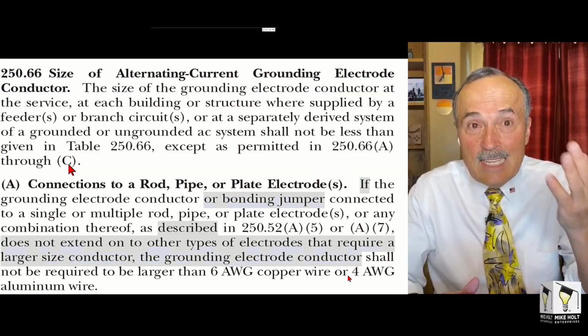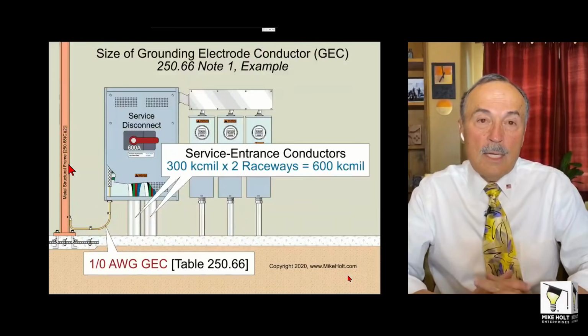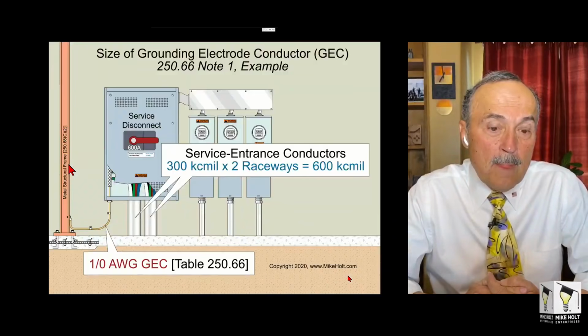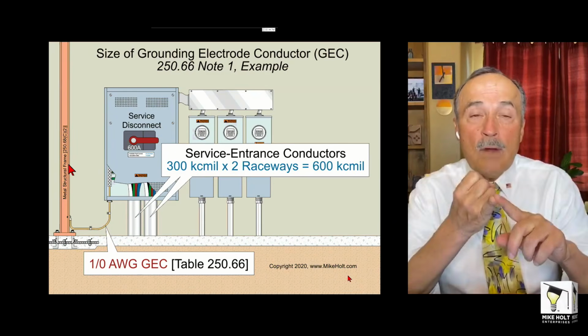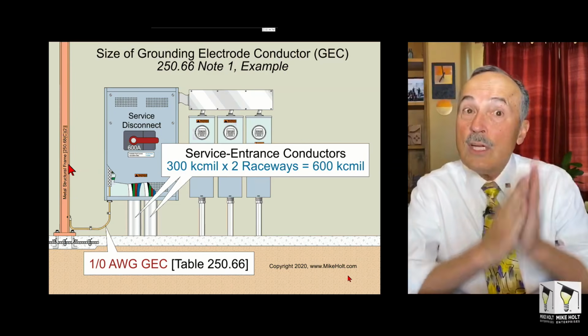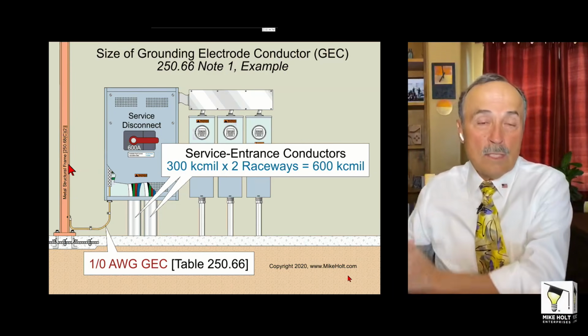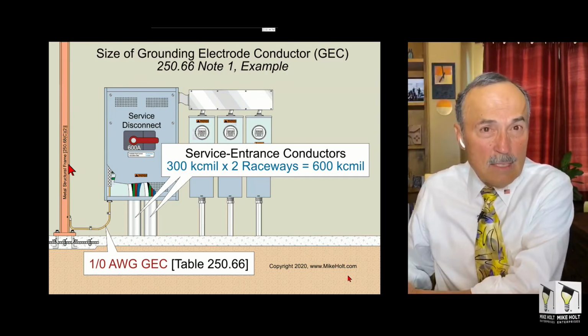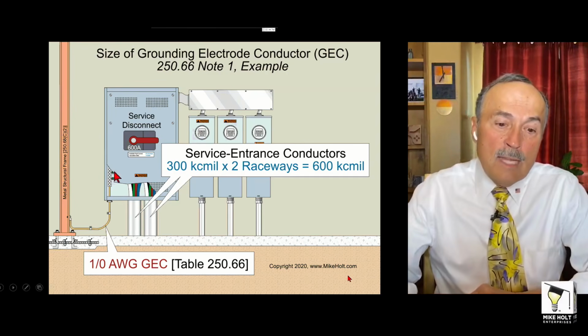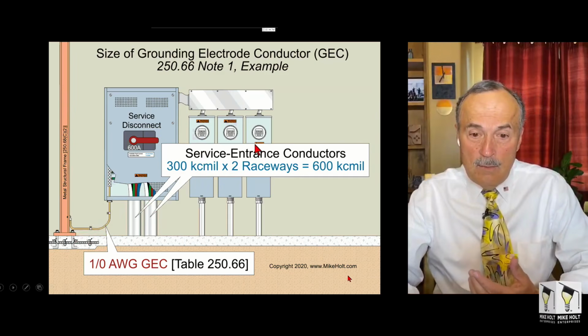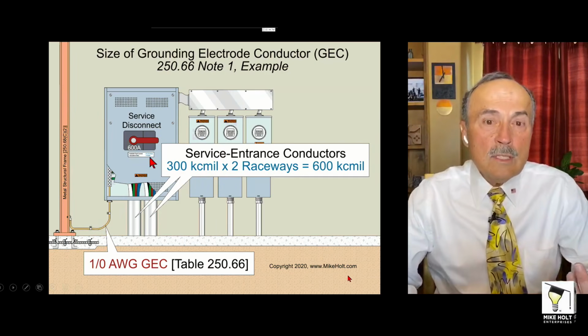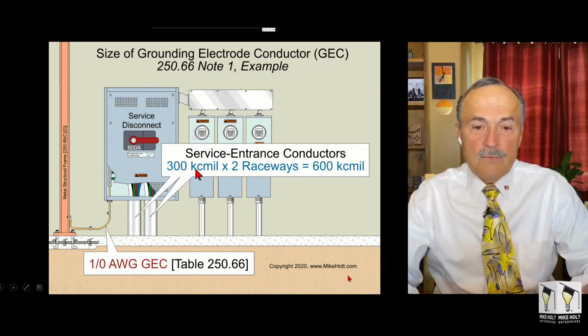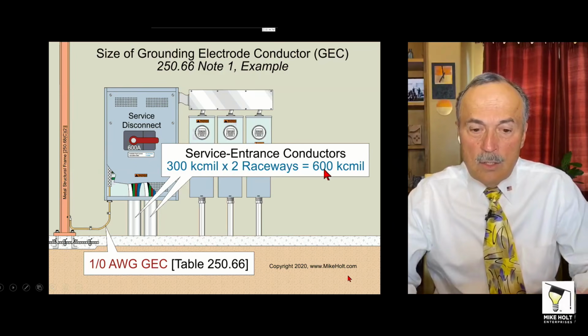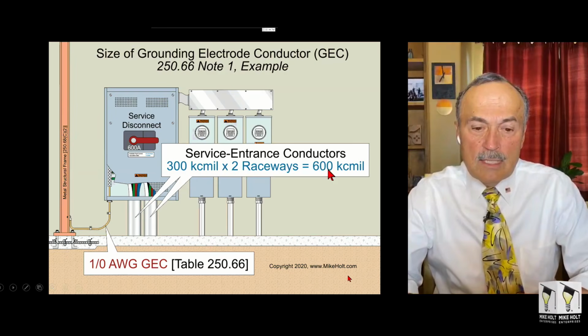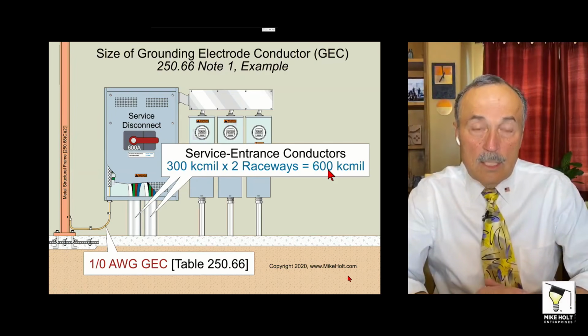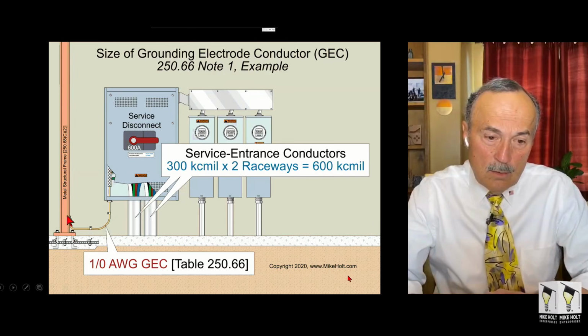So if it's not any of those, let's say you go into structural steel, then you have to go to the table because it's not a ground rod and it's not a concrete encased electrode, which means you have to go to the table unless it's a ground rod or a concrete encased electrode or the ring. Does that make sense? So now it would then be the full size. In this example, if we have a 600 amp service and we're paralleling 2 sets of 300 kcmil, and you go to the table and look up 600 kcmil, and it tells you 1/0, then I'd run a 1/0 conductor here.